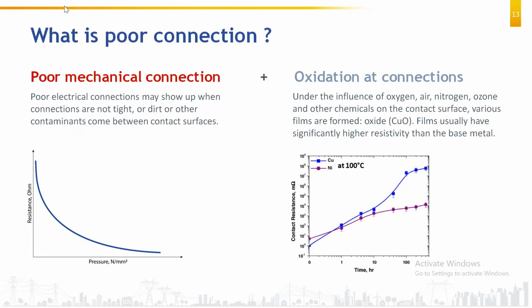So what is a poor connection? A poor connection can be because of two reasons: poor mechanical connection, or oxidation of the connection. In simple terms, a poor mechanical connection means the connections are not tight - if your nut bolt or whatever connection you are using is not tight, then you have a poor mechanical connection. Poor electrical connections may also show up because of dirt or other contamination between contact surfaces.